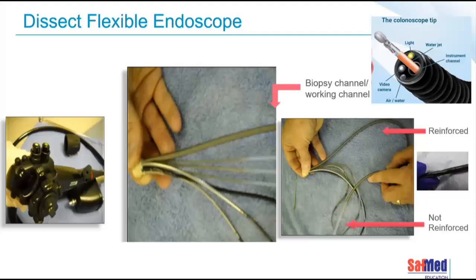In here, you can see the biopsy channel, which we also refer to sometimes as the instrument channel or the working channel. Now, that very first part of the biopsy channel from the distal tip is reinforced. You can see that there's a nice metal section to it, but past that, it is not reinforced, and it's merely a piece of plastic tubing.